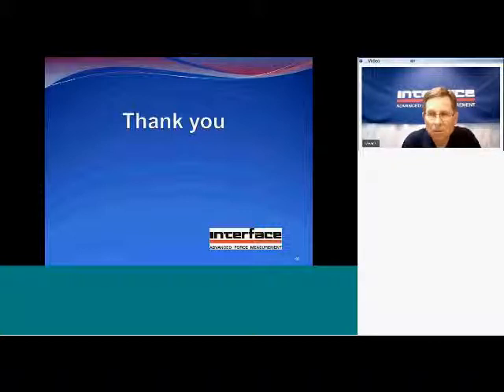Creep is a good single number to use because any load cell that has low creep generally has good quality construction. So if you were to pick a single number, creep might be that number. But again, it depends on your application. What's really important is the long-term stability, and you don't get that off of a data sheet. So you can take your load cell and monitor it over time. As you see that we have done with our standard load cells, that history that we have on them is priceless.